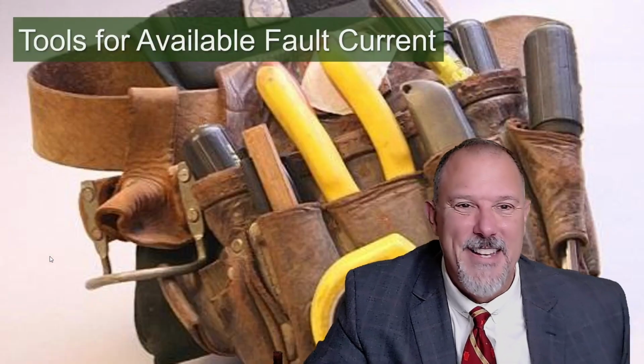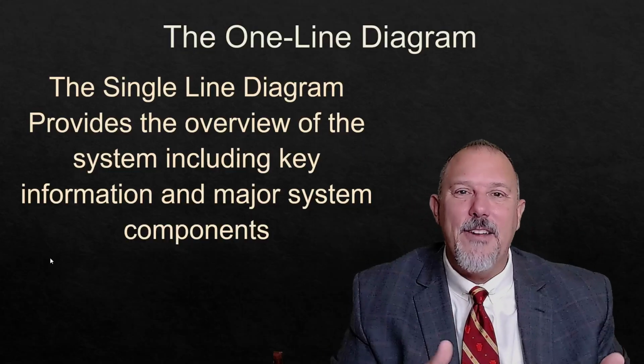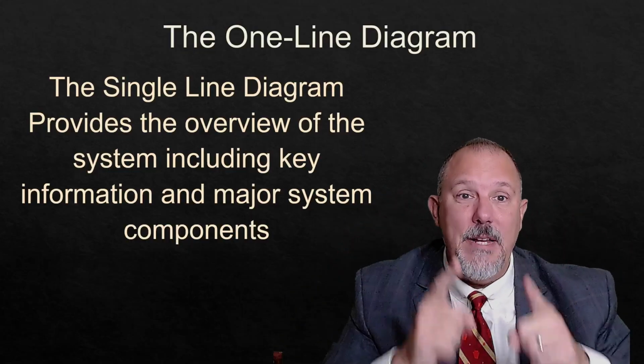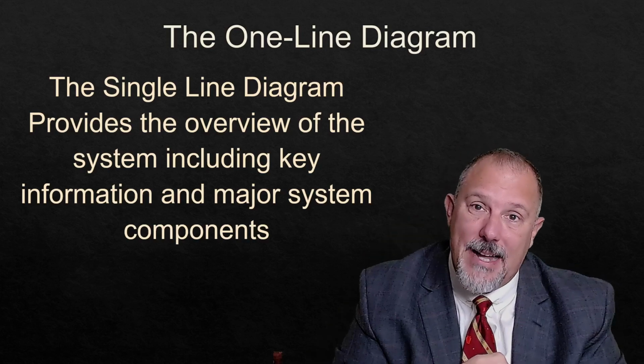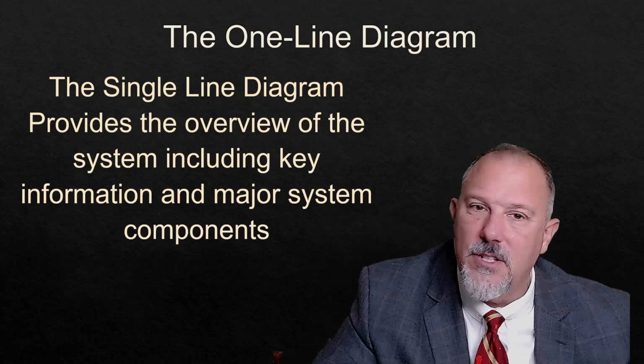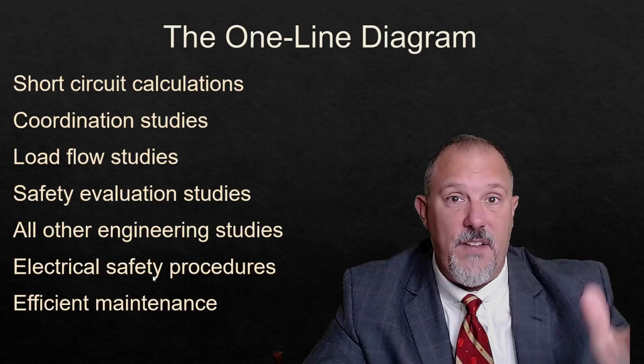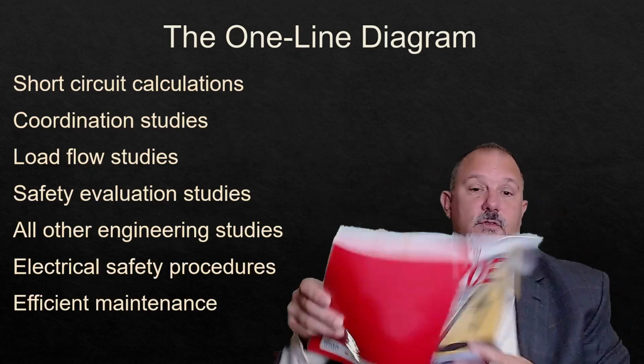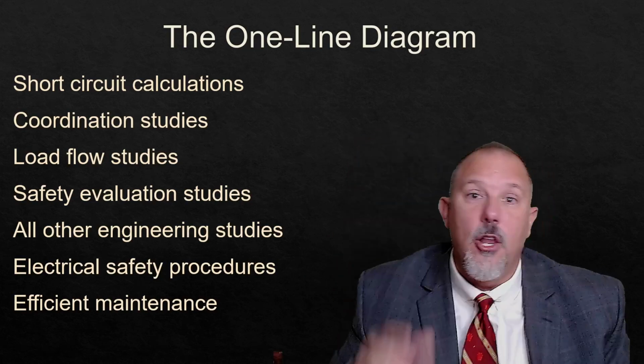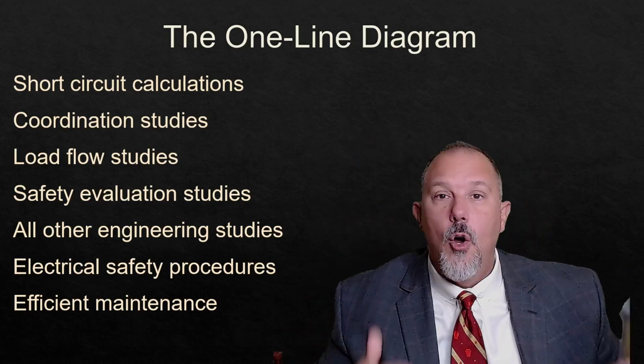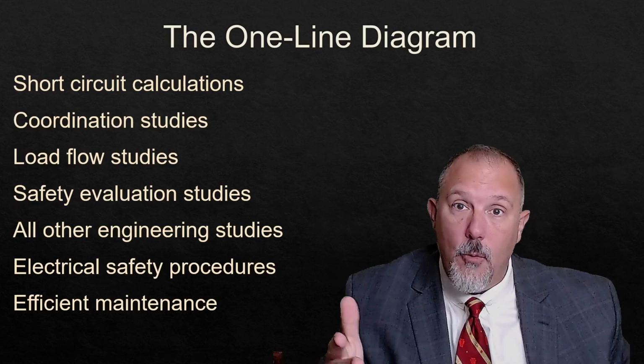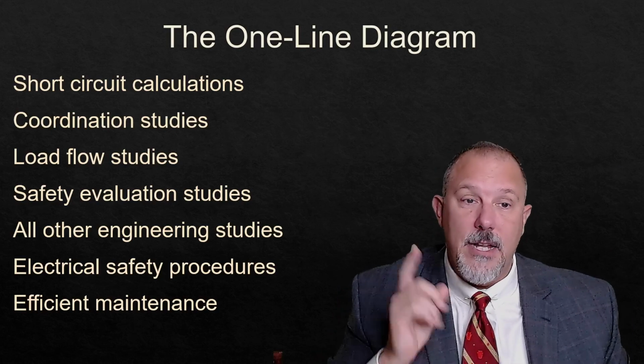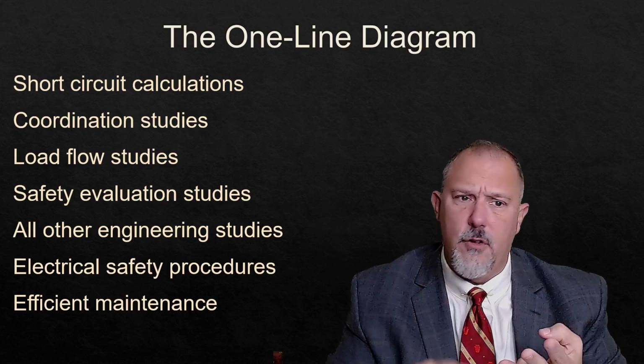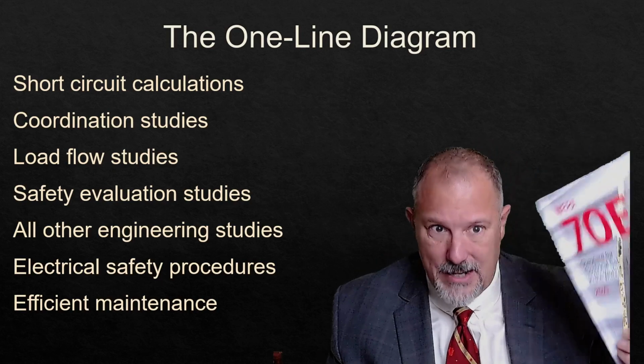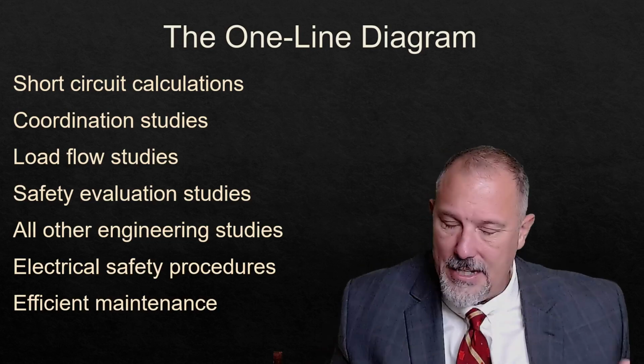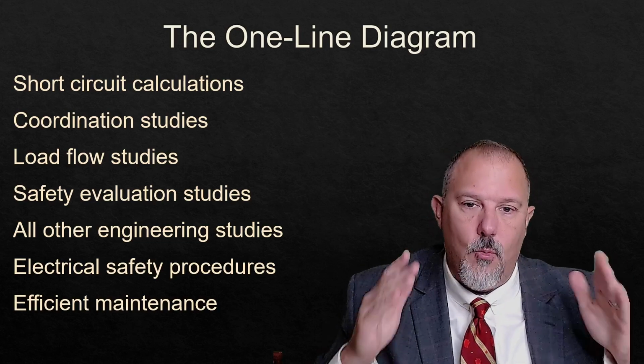All right, tools. The one-line diagram, the number one tool. You need to make sure you have the latest single-line diagram. The single-line diagram has a lot of information, and it is critical for electrical safety, for safe work practices, for 70E, lockout, tagout. How do you do lockout, tagout without an accurate one-line diagram? Help me. Short circuit current calculations, I need it for coordination studies, load flow studies, safety evaluations, lockout, tagout programs. Any engineering study that you're going to do is going to need a one-line diagram.